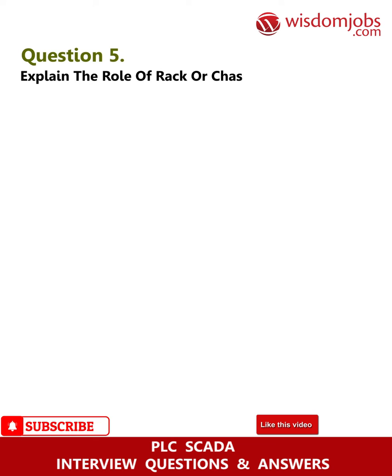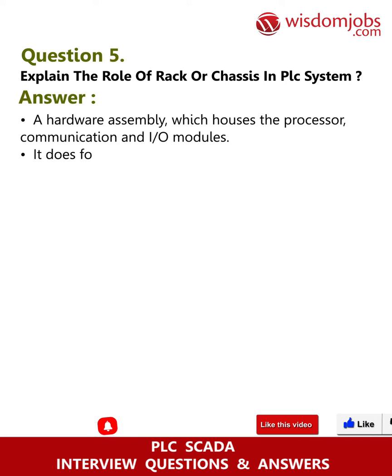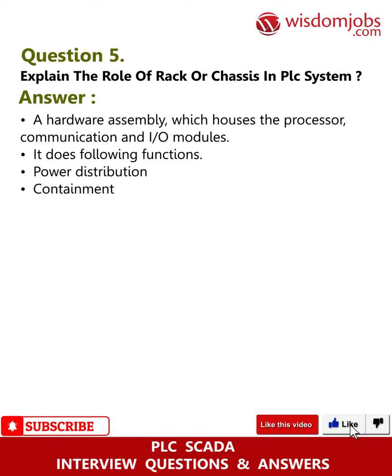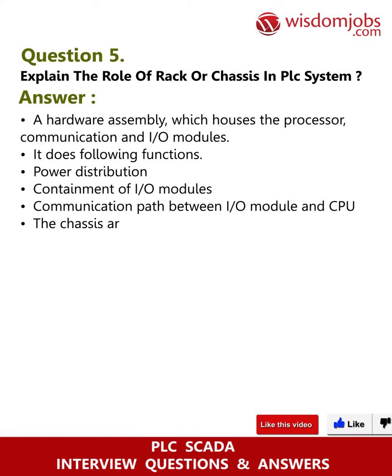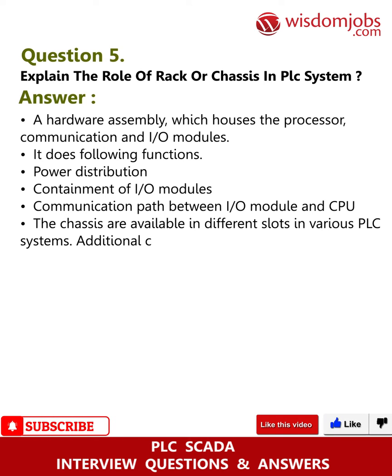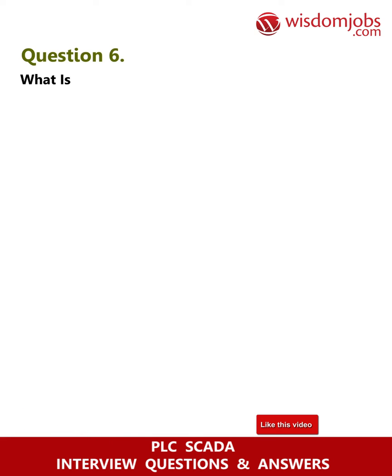Question 5: Explain the role of rack or chassis in a PLC system. Answer: A hardware assembly which houses the processor, communication, and IO modules. It performs functions such as power distribution, containment of IO modules, and providing a communication path between IO modules and the CPU. Chassis are available in different slot sizes in various PLC systems, and additional chassis can be connected using chassis interconnecting cables.